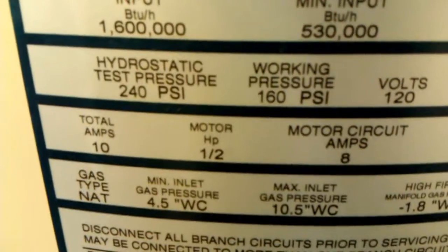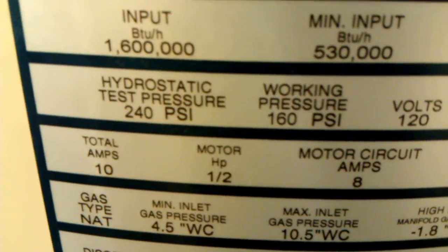There's the capacity of it. Now this could be controlled entirely just from this TempTrak controller. However, this is just stage one of multiple boilers by another controller that's sensing a water tank. But I do have this programmed to where once it gets near the shutoff point, it starts modulating down.